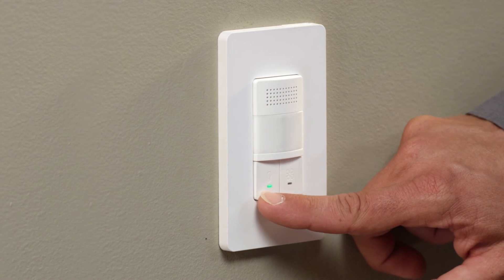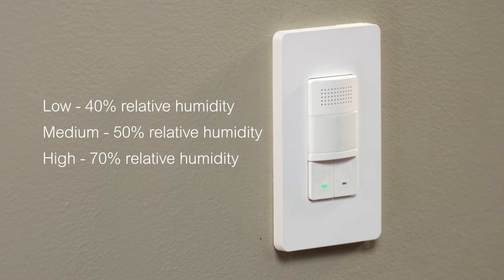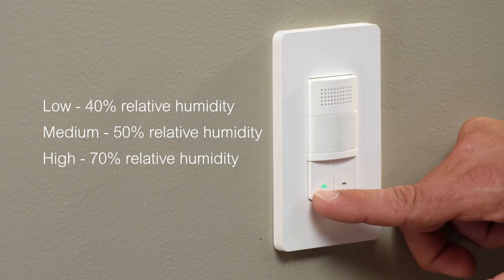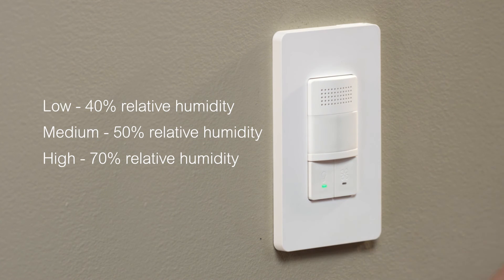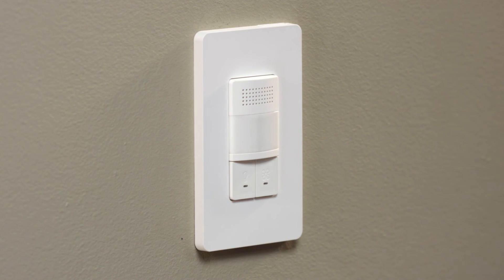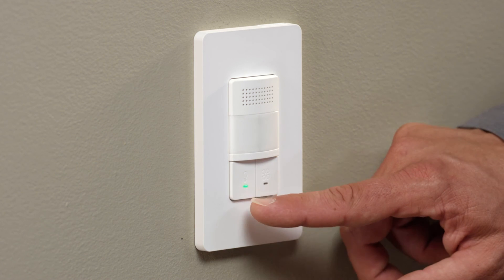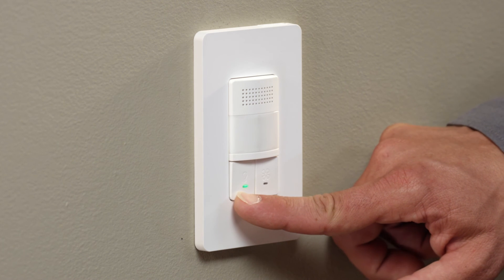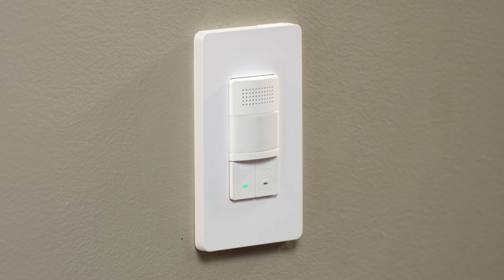One more press of the light button will set the humidity level at low, the factory default. Two more presses will set it at medium and three more presses will set it at high. The light indicator will blink 10 times confirming that you have changed the humidity set point. Press and hold the light button for 5 seconds to save the current setting and exit the configuration state.